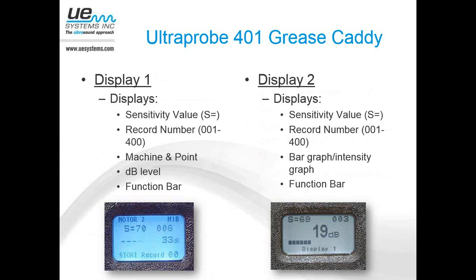So those are our 2 display panels that we can set this up with. First of all, display 1 is going to show us the sensitivity value and our record number. If we need to load a route into it from DMS, it's going to show the machine and the point name, and the decibel level, which you can see again is similar to some of our other Ultraprobes. You'll see this blinking arrow pointing to either the right or to the left, letting you know where you need to set the sensitivity. Once you've got the sensitivity into range, that's where you'll see your decibel level. And then the function bar.